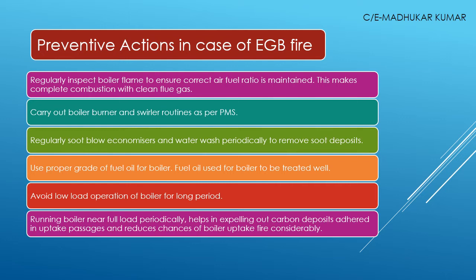Use the proper grade of fuel oil for the boiler — residual fuels inevitably give residues, soot, or unburnt carbon particles, but lighter fuels produce less, or if fuel is properly treated and perfect combustion conditions exist, you get clean flue gases. Avoid low load operation of the boiler for longer periods, as this is a main cause of incomplete combustion and incorrect air-fuel ratio. Running the boiler near full load periodically, or the main engine running at 85% MCR, helps expel carbon depositions due to higher exhaust gas velocities, keeping the uptake passages clean and reducing the chances of boiler uptake fire.